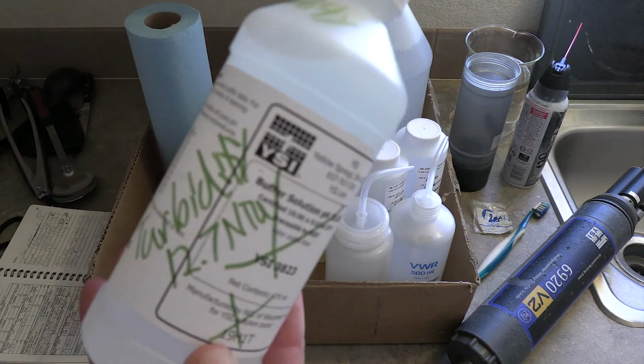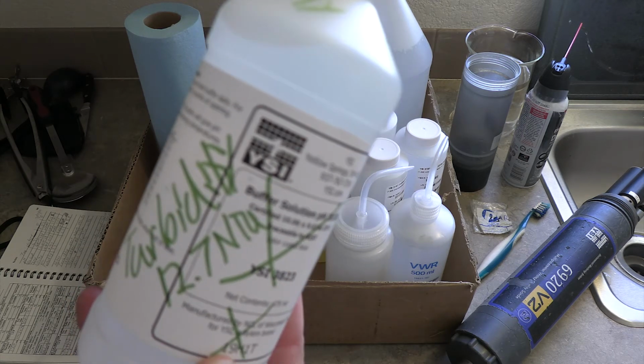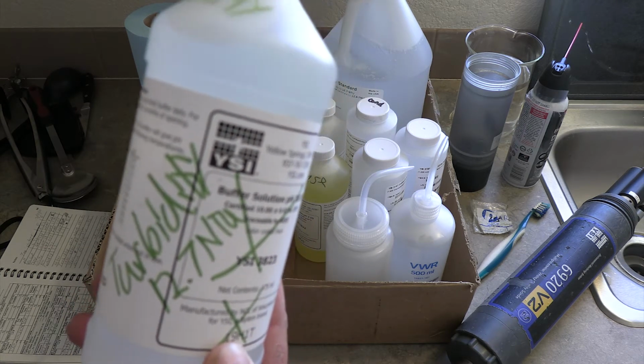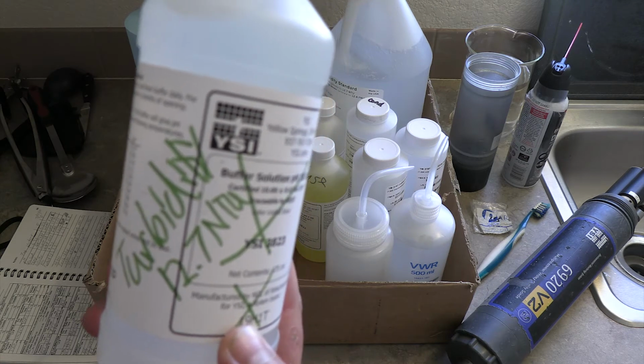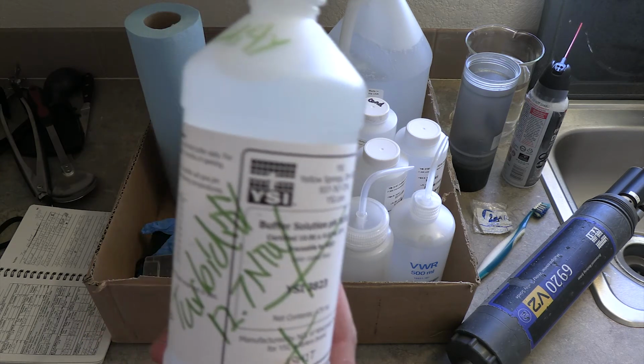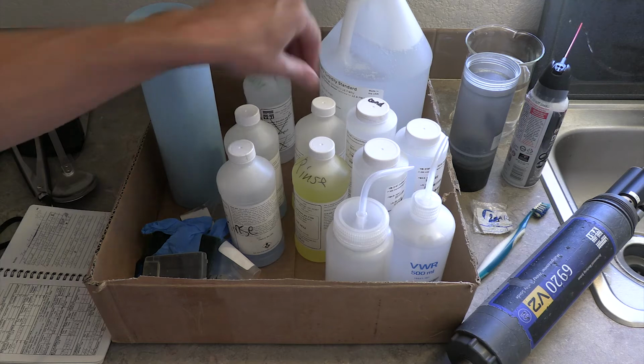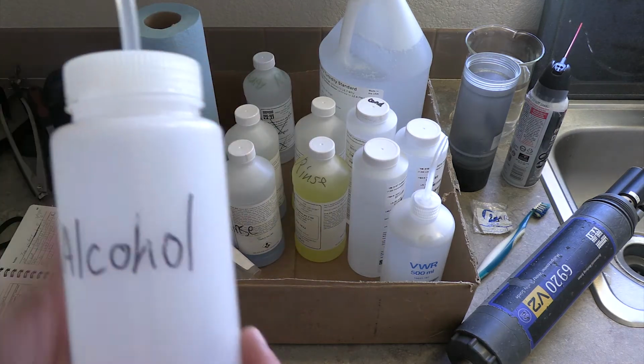And other than that, the turbidity is pretty straightforward, and then I just keep on hand a small bottle with the turbidity rinse. So just rinse with this beforehand, to clean it and prep it for turbidity itself. And that does it for all the solutions for calibration, other than alcohol for cleaning, if you want to clean the joints and stuff.